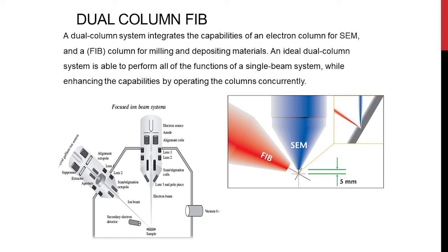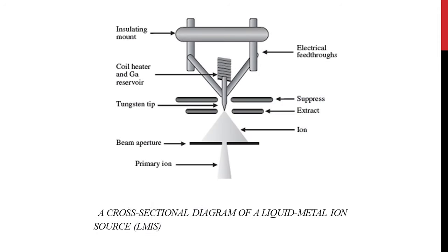Let us look at the schematic of a dual beam system. It is a combination of two beam systems — the electron column at 0 degrees and the ion column is located at an angle of 52 degrees. This is a cross section of a source which is mainly used in the focused ion beam. In focused ion beam, we use a liquid metal ion source, which is basically gallium, because of its very low melting point. We have a reservoir of gallium which is heated to a certain temperature, and then we have a tungsten tip attached to the reservoir.